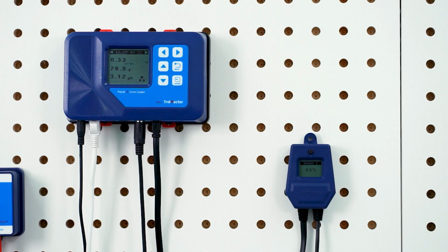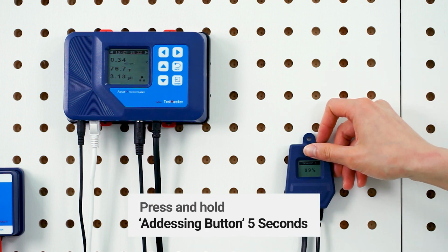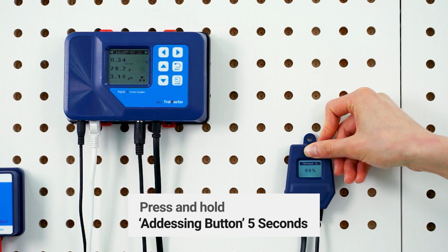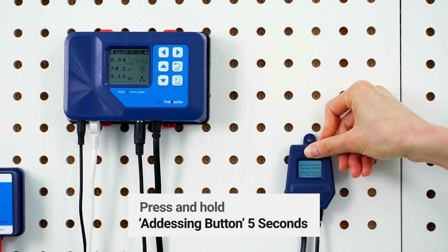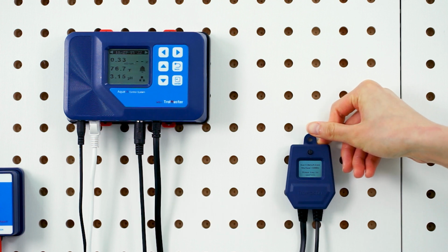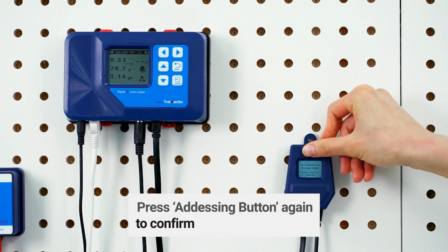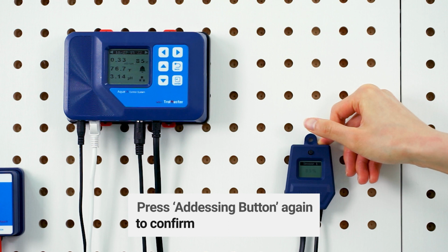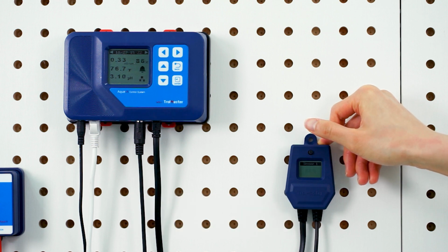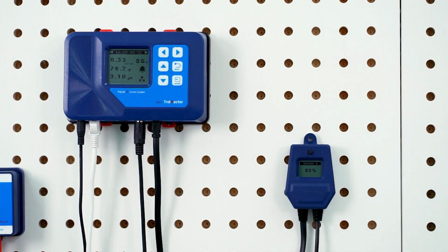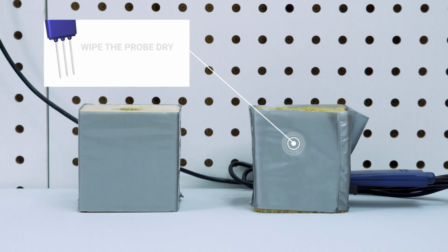We'll calibrate it to 100%. Be sure the pins are inserted all the way in. Then press and hold the addressing button for 5 seconds. And press the addressing button again to confirm. After you've done calibrating it to 100%, remove the probe and wipe it dry.